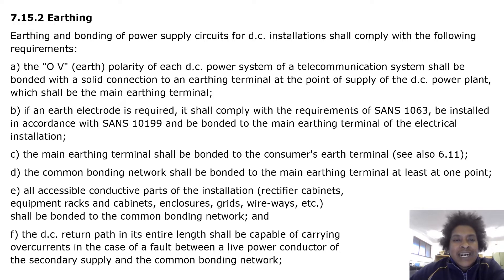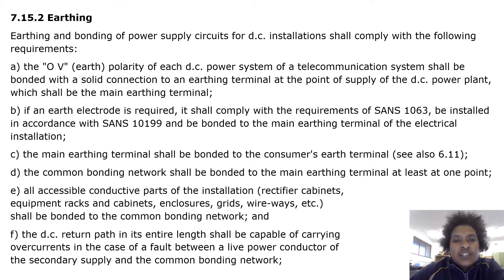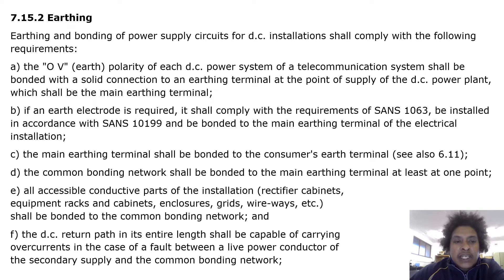Earthing and bonding of power supply circuits for DC installations shall comply with the following requirements. The zero voltage earth polarity of the DC power system of a telecommunication installation shall have a solid connection to the earthing terminal at the point of supply of the DC power plant, which shall be the main earthing terminal.